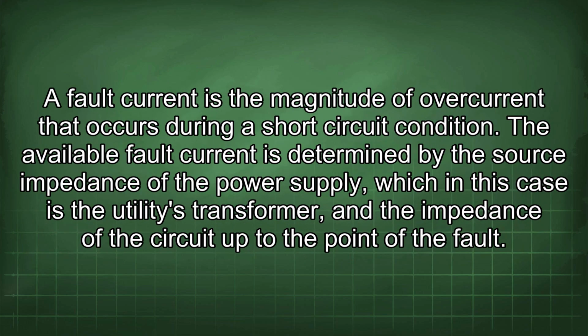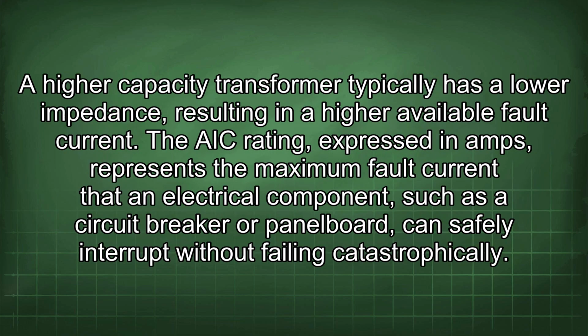A fault current is the magnitude of overcurrent that occurs during a short-circuit condition. The available fault current is determined by the source impedance of the power supply, which in this case is the utility's transformer, and the impedance of the circuit up to the point of the fault. A higher capacity transformer typically has a lower impedance, resulting in a higher available fault current.